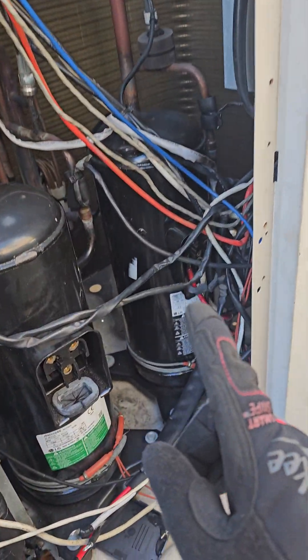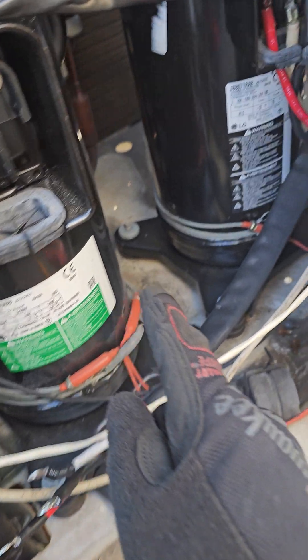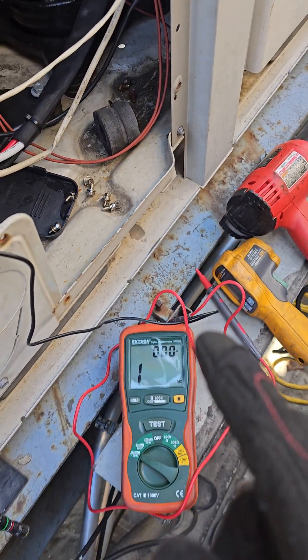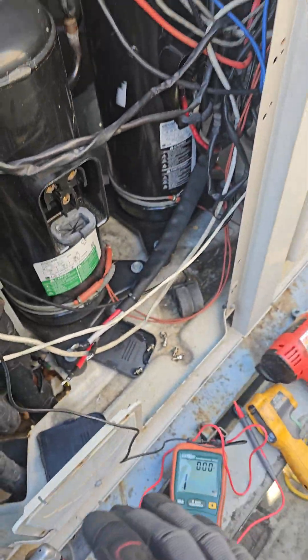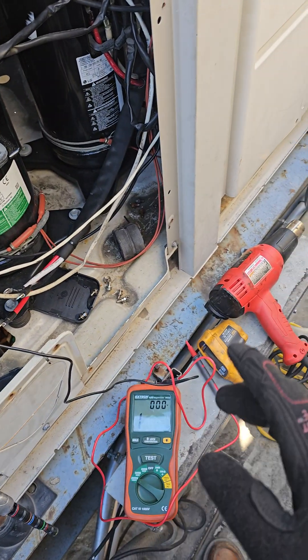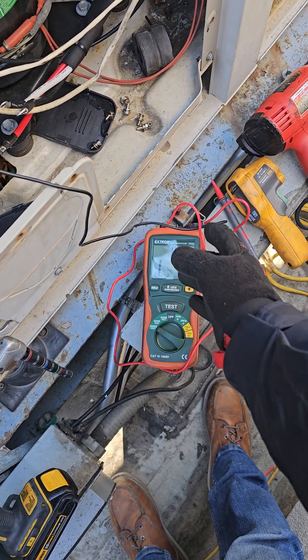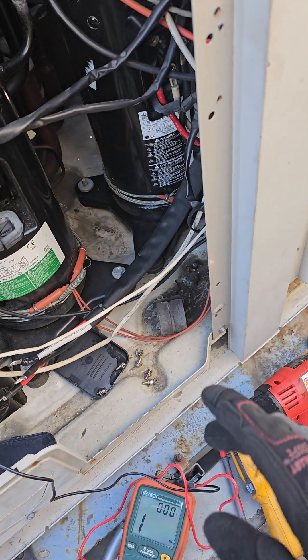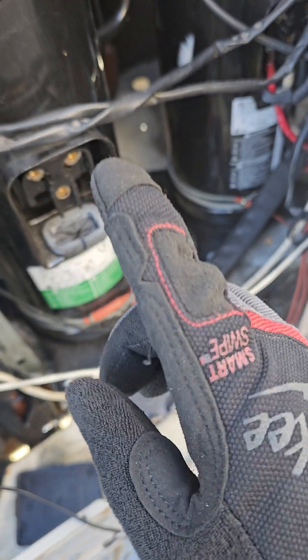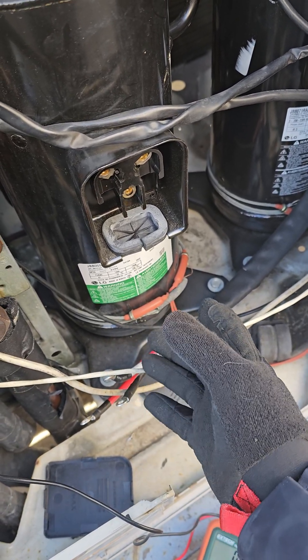In this LG multi-V unit, all these compressors use the inverter compressor — that's the standard compressor that failed the megger test. We had a proven bad unit with error 26, stating the compressor failed to start. When we did the megger test, all of them failed. After leaving the crankcase heaters powered up for 12 hours, most passed with flying colors.